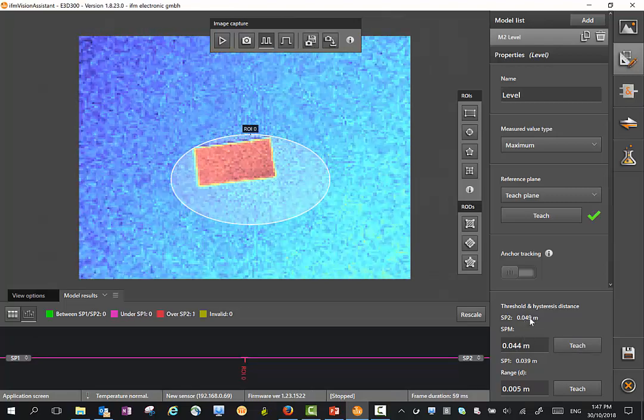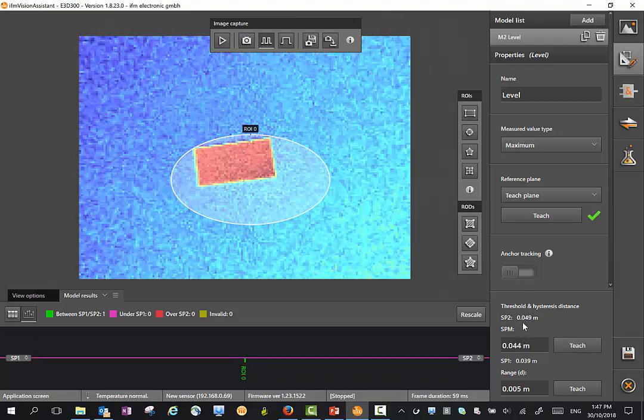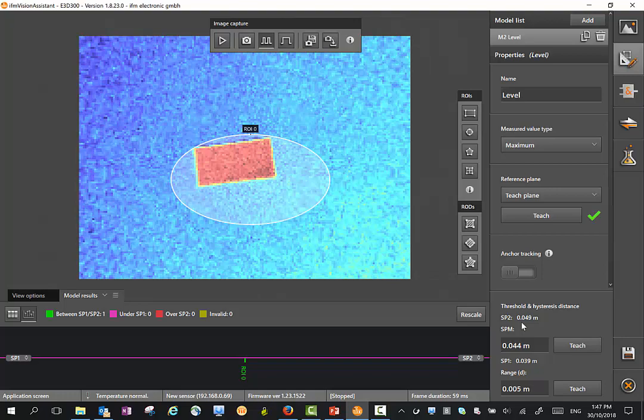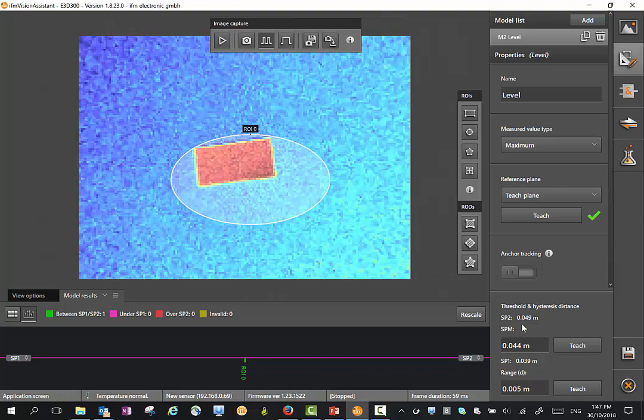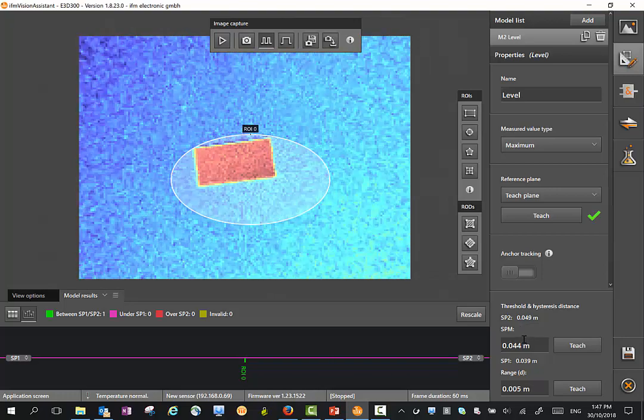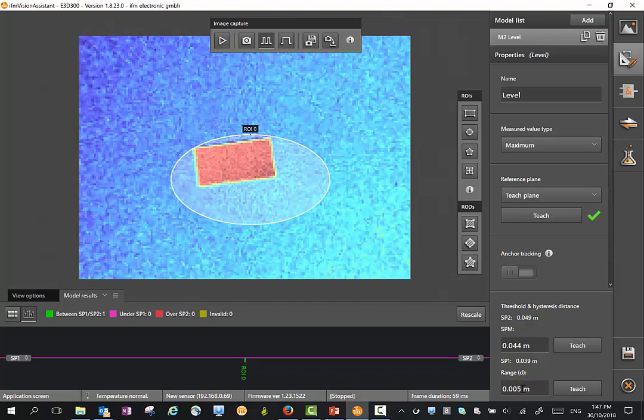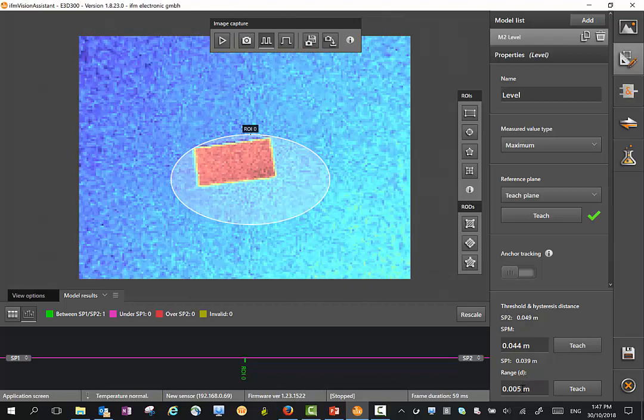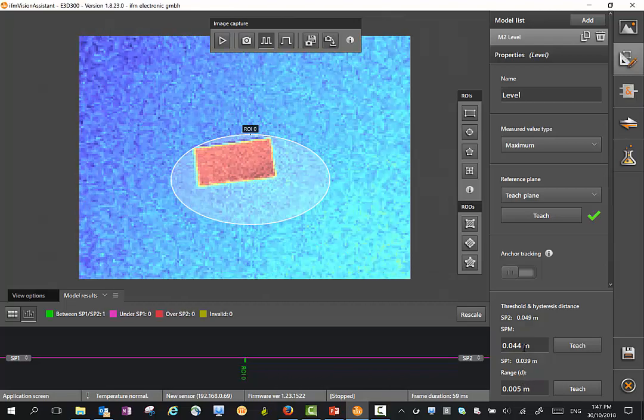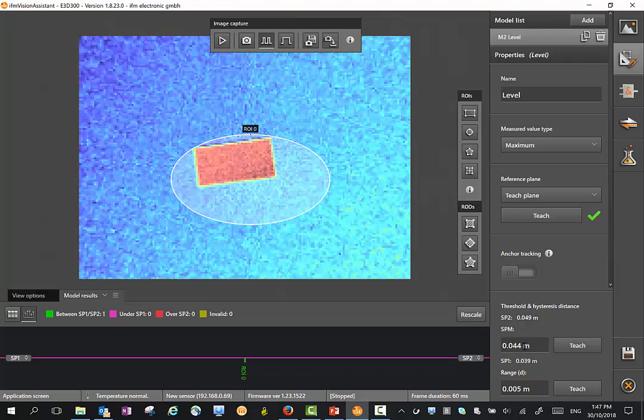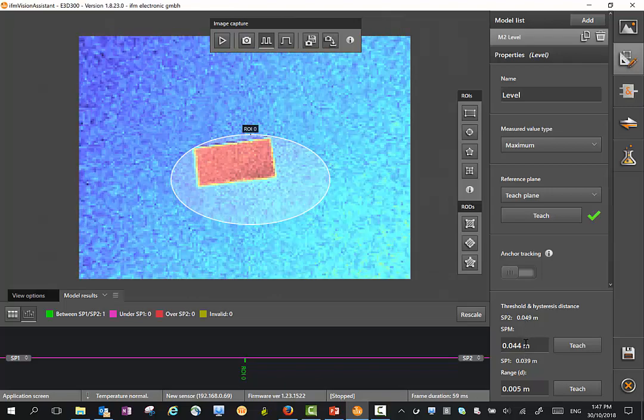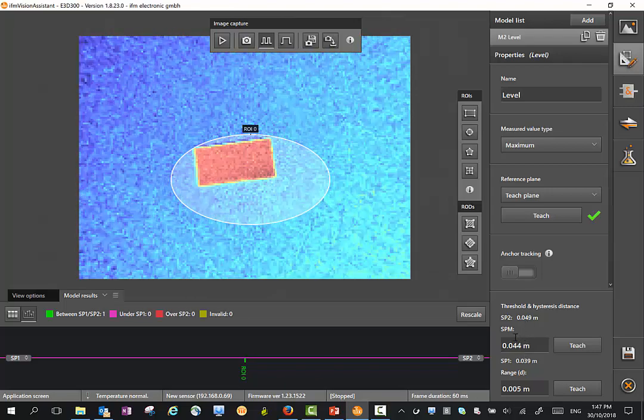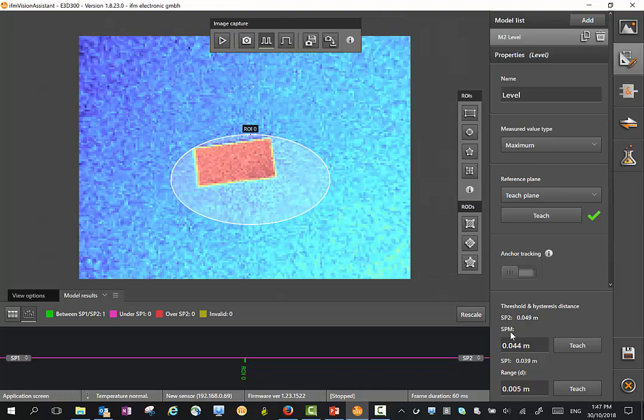Please make note of the set points here as well. Because the hysteresis is actually above and below the actual set point. You'll see at the moment I've got a hysteresis of 0.005 of a meter, and it's applied to this midpoint here. So the actual switch points are above and below the midpoint of the set point.